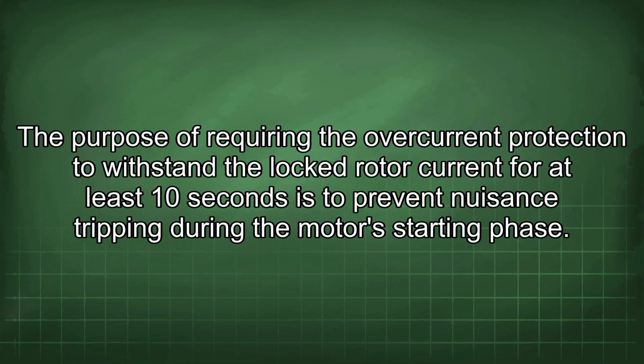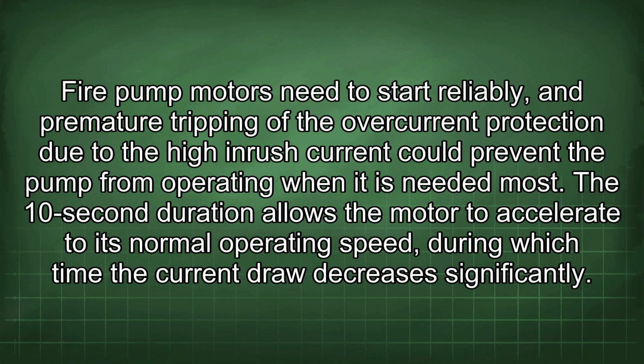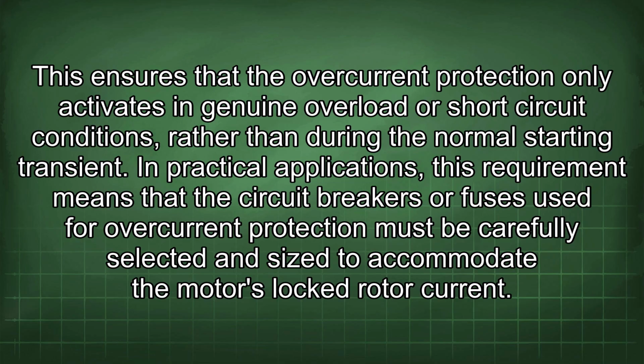The purpose of requiring the overcurrent protection to withstand the locked rotor current for at least 10 seconds is to prevent nuisance tripping during the motor's starting phase. Fire pump motors need to start reliably, and premature tripping of the overcurrent protection due to the high inrush current could prevent the pump from operating when it is needed most. The 10-second duration allows the motor to accelerate to its normal operating speed, during which time the current draw decreases significantly. This ensures that the overcurrent protection only activates in genuine overload or short circuit conditions, rather than during the normal starting transient.